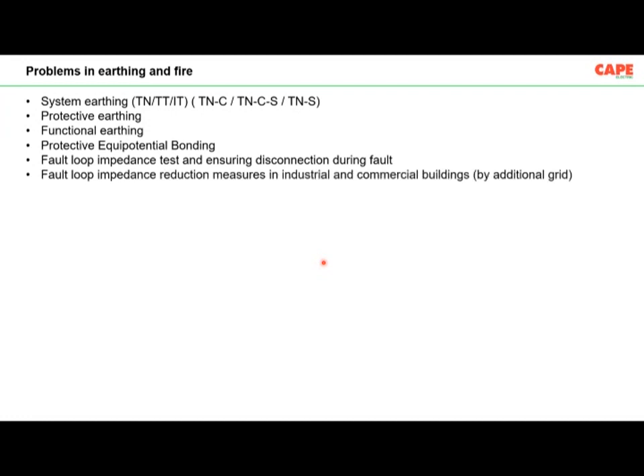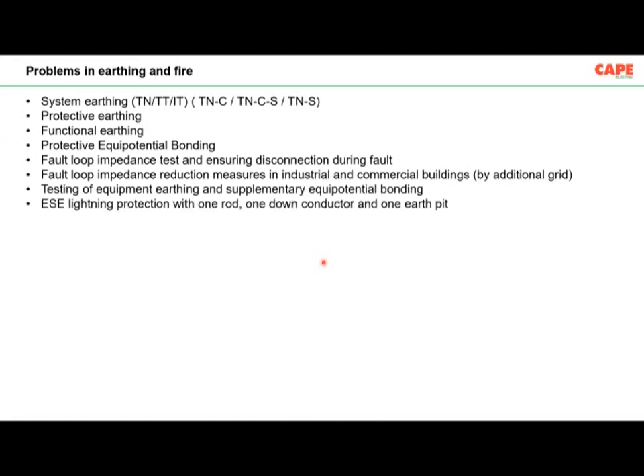Functional earthing means for the operation of electronic equipment, you are supposed to connect it as I said in one of the slides. Instead, what we do, we take a wire and connect the equipment to an earth pit in soil. This is wrong. Protective equipotential bonding mostly is a problem. Fault loop impedance test and ensuring disconnection during fault is also very rarely done. Fault loop impedance reduction measures in industrial and commercial buildings by additional grid is also a little bit problematic area. Testing of equipment earthing and supplementary equipotential bonding. Say, for example, like you have a lift or you have a large machine or you have an operation theater, supplementary equipotential bonding and the continuity resistance measurements we rarely do.